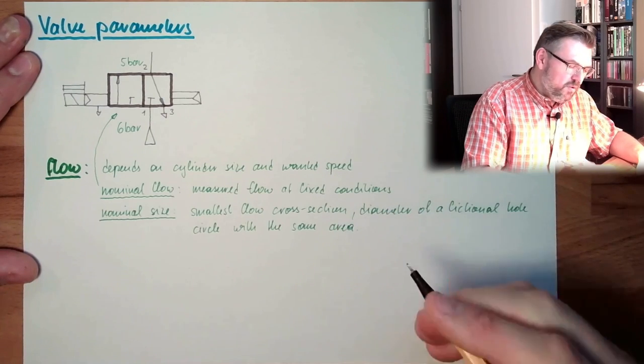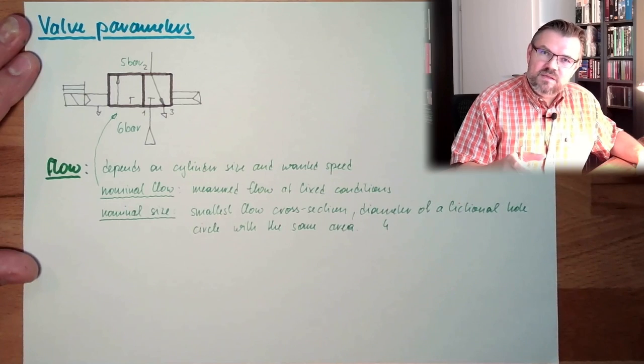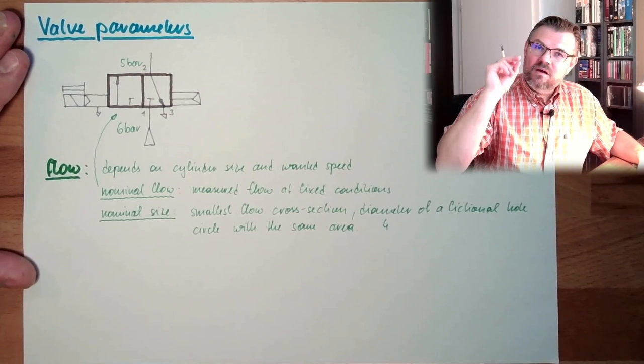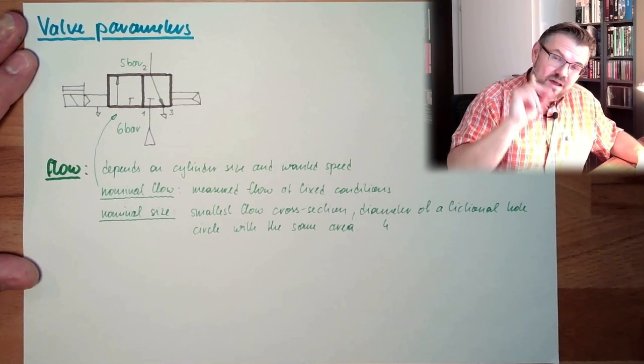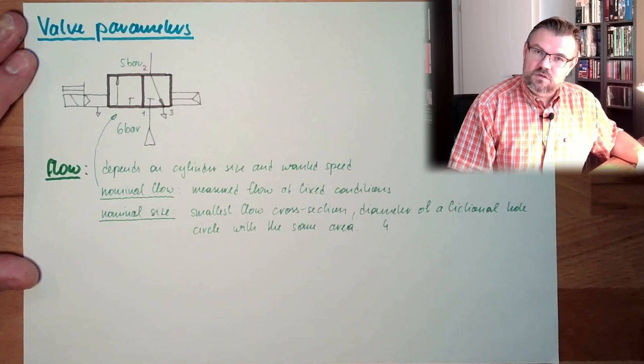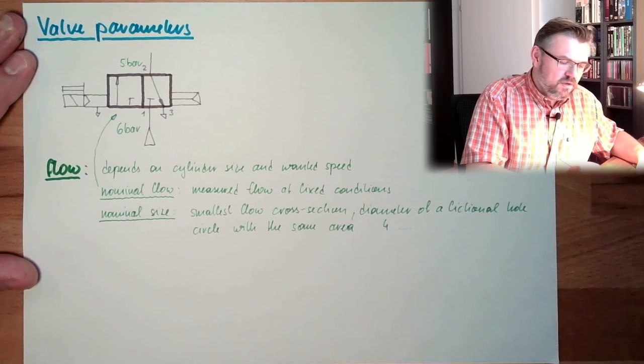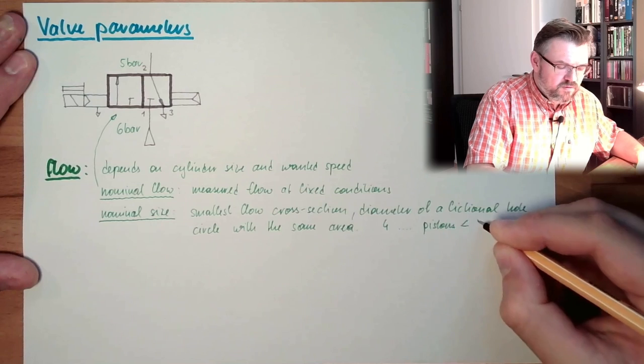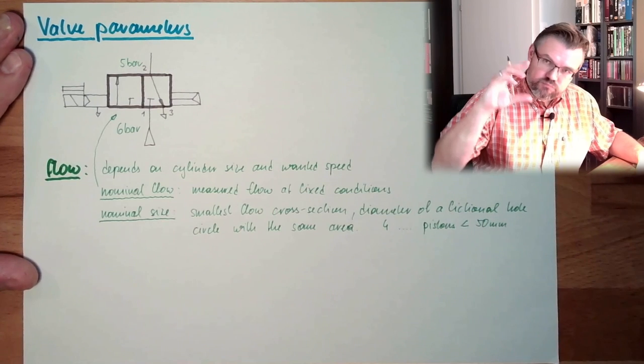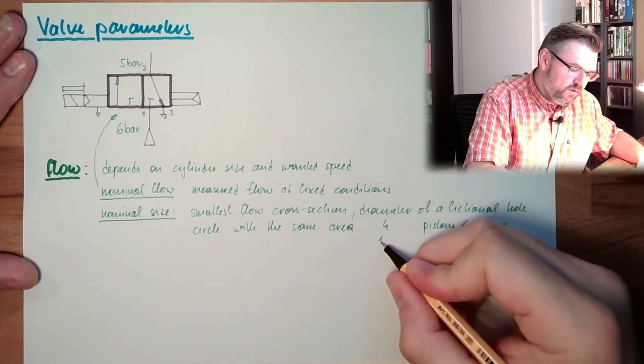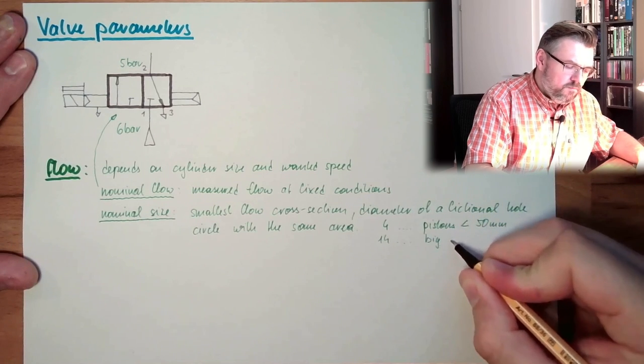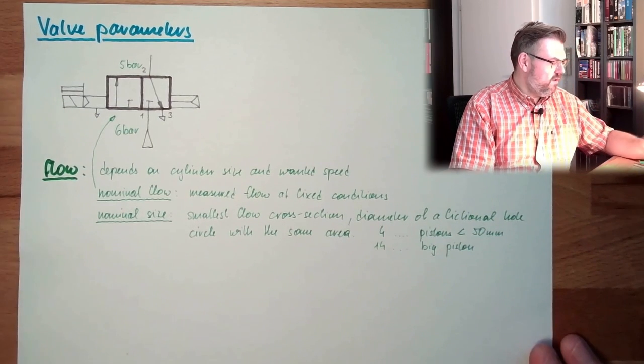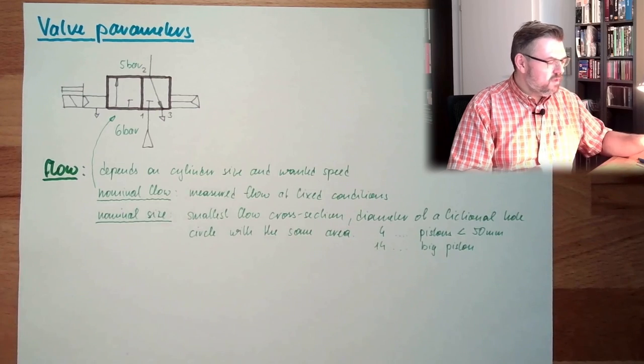So, if we have nominal size number 4, then it's 4 millimeters. You do not find this 4 millimeters somewhere, there is no hole with 4 millimeters. It just means a 4 millimeter round hole would have the same area as the smallest flow cross-section. And this 4, nominal size 4, they are usually for, in the pneumatic world again, pistons smaller than 50 millimeters. And there are 14, for instance. This is then for big pistons, big size. In this area we usually are. So flow, this is one big topic.